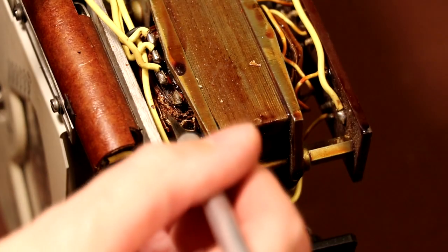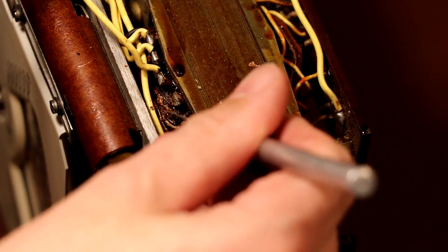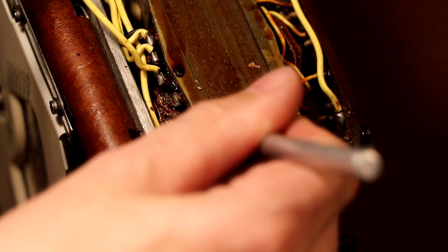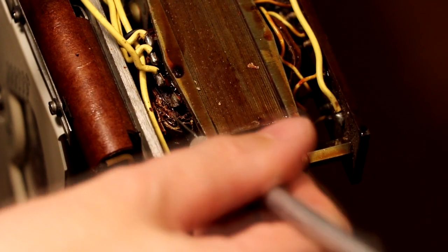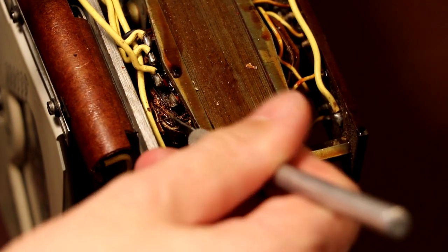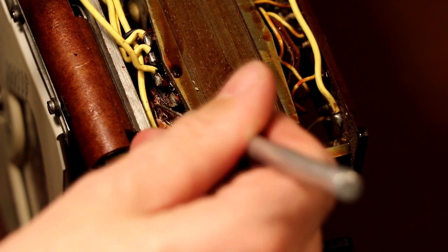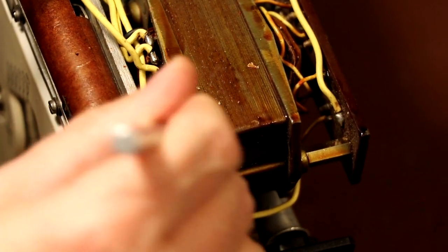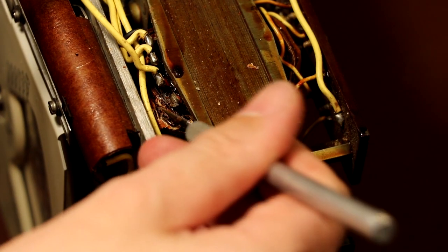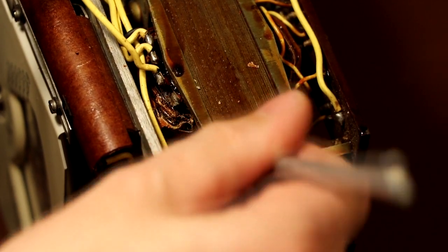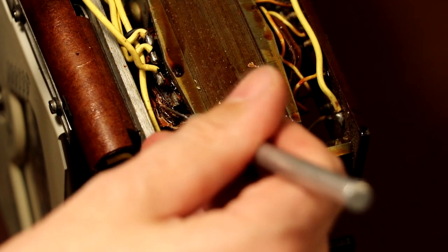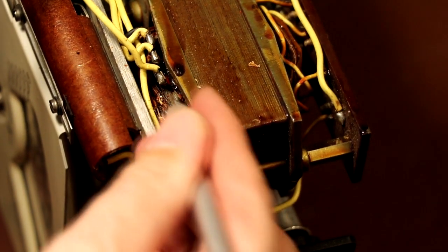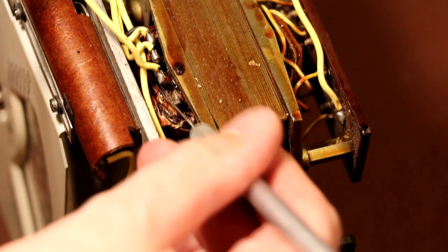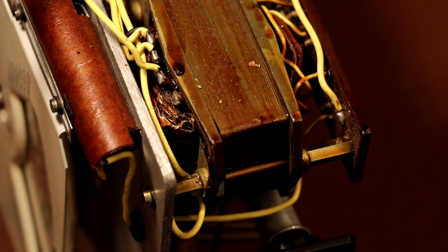I'm not sure how well this is coming up on camera, but now I've actually bothered to scrape away some of the varnish on here. I can see that the windings are very discoloured, very burnt looking, so I'm fairly sure at some point in the past this transformer has got very, very hot, and one of the secondaries has shorted out. Actually, it's not shorted out anymore, it's actually burnt out, and luckily it went open circuit. Now of course it's impossible to tell if that happened when somebody destroyed the input attenuator.